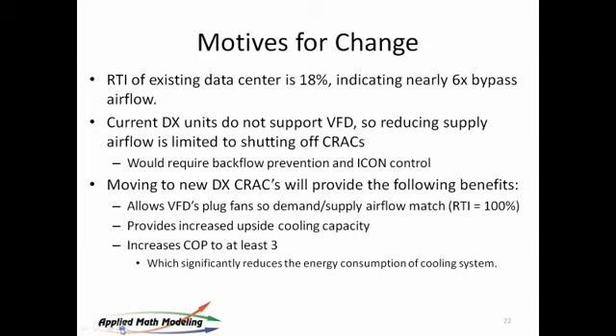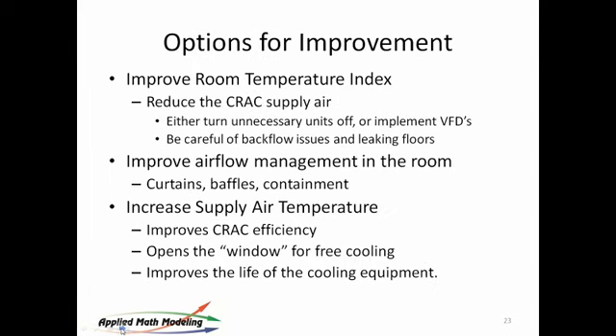And if you were to go to new DX units, there is some advantage because you can put VFDs on new DX units, but I will point out that they don't go down that low. For a data center like this, you couldn't get rid of the amount of airflow you need to get rid of, because they only move down about 20%. That's my experience. And modeling can allow you to understand, of course, the effect. So the first thing we're going to do is improve RTI by shutting units off. Then we're going to improve the air management of the room, and then we're going to walk up the supply air temp to improve the efficiency of the CRACs.